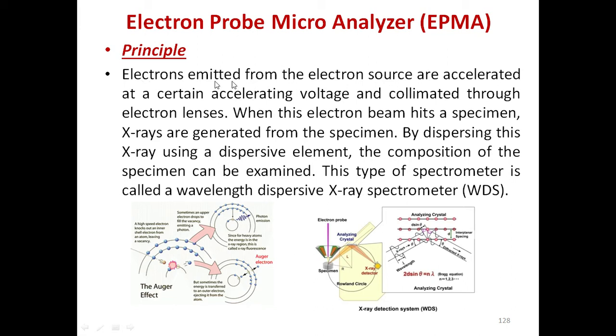Principle: electrons emitted from the electron source are accelerated at a certain accelerating voltage and collimated through an electron lens. When the electron beam hits the specimen, X-rays are generated from the specimen. By dispersing these X-rays using a dispersive element, the composition of the specimen is examined. This type of spectrometer is called a wavelength dispersive X-ray spectrometer, or WDS. It works on the same principle as XRD, that is, on Bragg's equation.